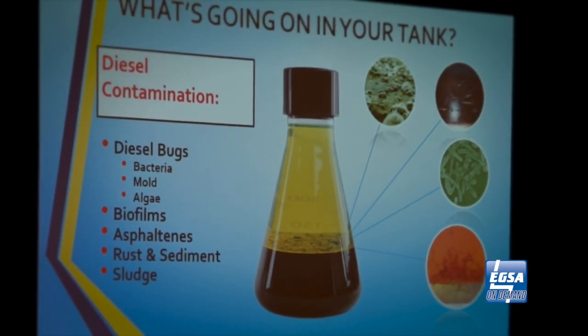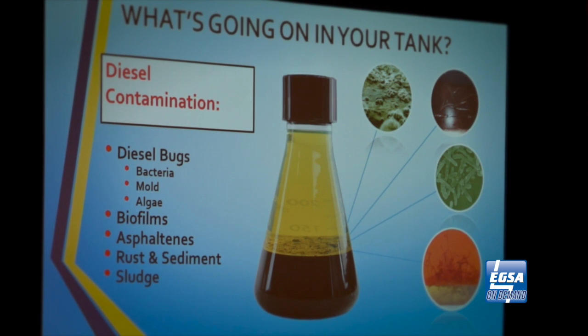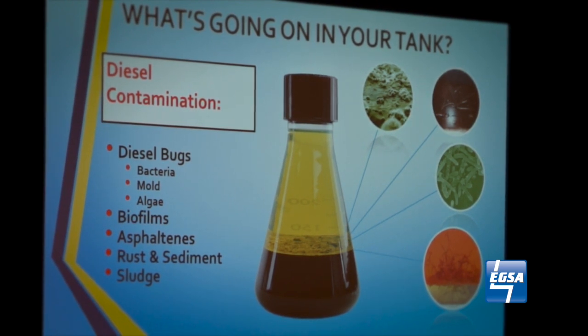As they grow, they create byproducts — some are weak acids, some are sludge, asphaltenes, and other harmful byproducts. The weak acids are concerning most because they create rust and corrosion in the bottom of the tank. But they also have a vapor pressure higher than the diesel, so they migrate through the diesel and contaminate the top of the tank and the whole head space. We're seeing cases where, through condensation and heating and cooling of the day, water accumulates on top, and then rust rolls down the side and ends up on the bottom of the tank where your pickup tube is. Most generators fail about two hours after a PM because the engine is just churning up all the garbage on the bottom — the biofilms and sludge — and it plugs the filters. So you've got to control the water.